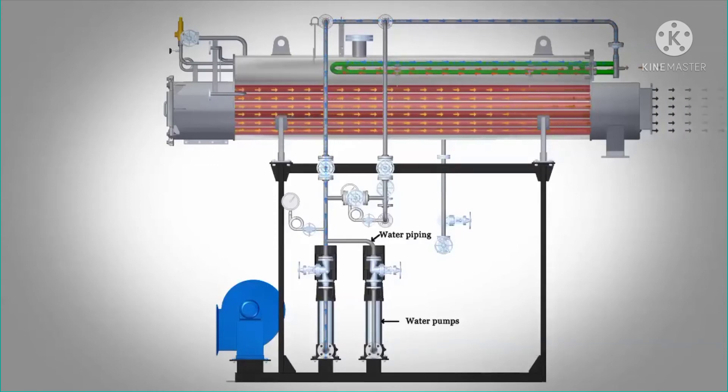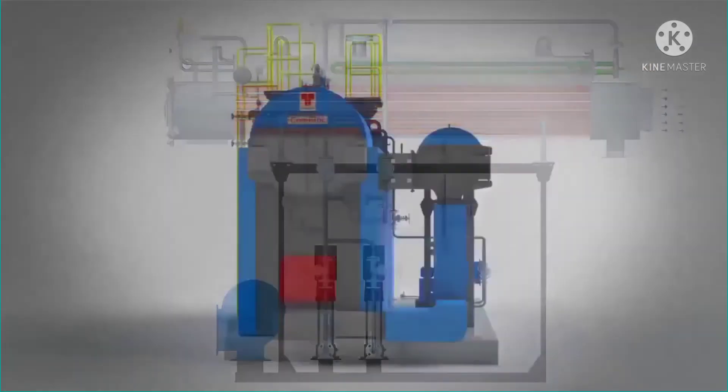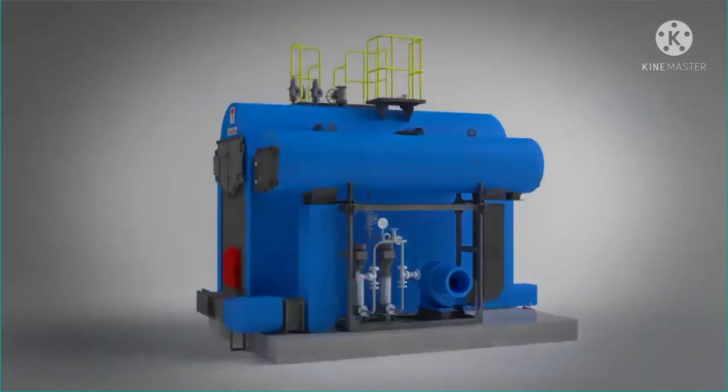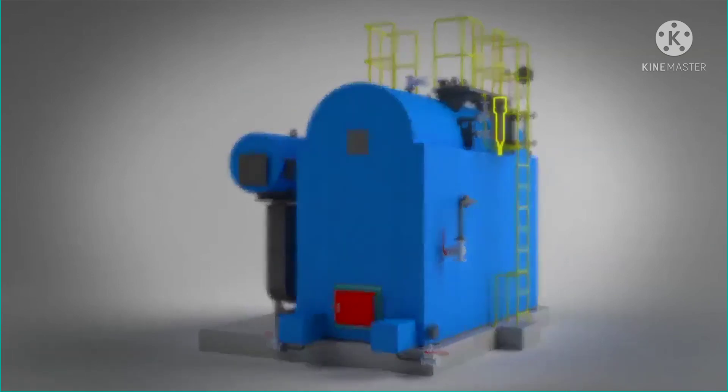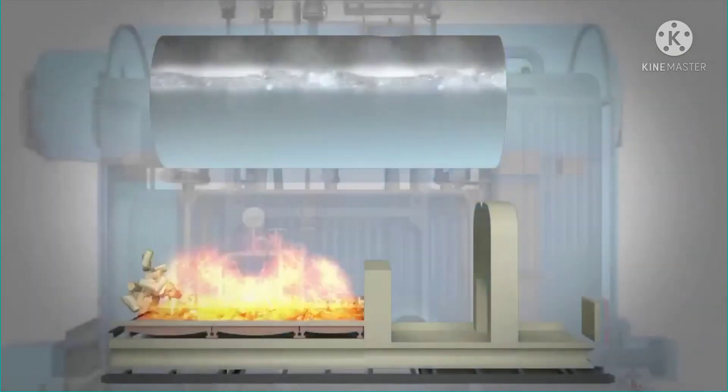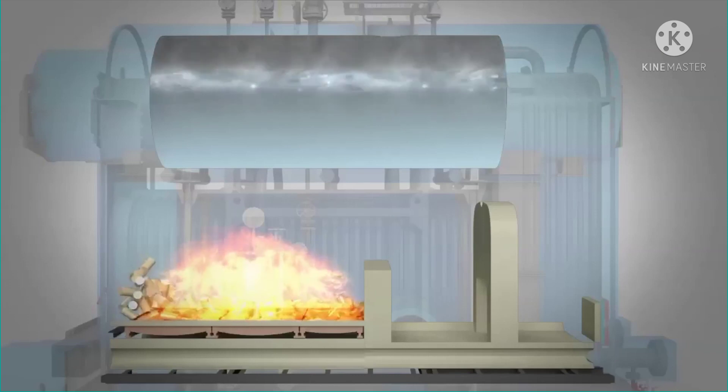Normally, two feed water pumps are provided, one of them being a standby. The level of water in the drum is maintained by using a device called a water level switch or transmitter. It is very important to keep the level of water in the drum higher than the topmost smoke tubes in the drum to ensure that these tubes are always immersed in water.